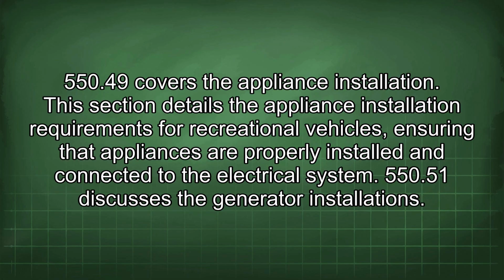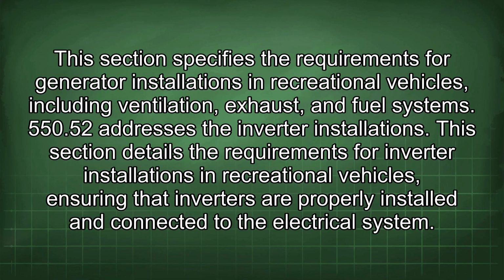550.49 covers the appliance installation. This section details the appliance installation requirements for recreational vehicles, ensuring that appliances are properly installed and connected to the electrical system. 550.51 discusses the generator installations. This section specifies the requirements for generator installations in recreational vehicles, including ventilation, exhaust, and fuel systems. 550.52 addresses the inverter installations. This section details the requirements for inverter installations in recreational vehicles, ensuring that inverters are properly installed and connected to the electrical system.